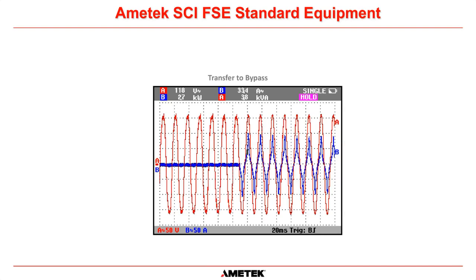And then what we also do, which is a very interesting picture, is we look at the transfer to bypass and then the transfer back to inverter. If you look at this waveform here, the red is the output voltage of the UPS, and the blue is the current flowing in the bypass. So up to this point here, there was no current flowing in the bypass circuit because we were on inverter. Okay. So what happened at this point here, somebody pressed the bypass to load push button and transferred the system to bypass. And you can see that there is no change in the output voltage whatsoever when that happened. So we know that that was a very good transfer. So we do that at every single annual PM. We make sure that the system transfers without a break.